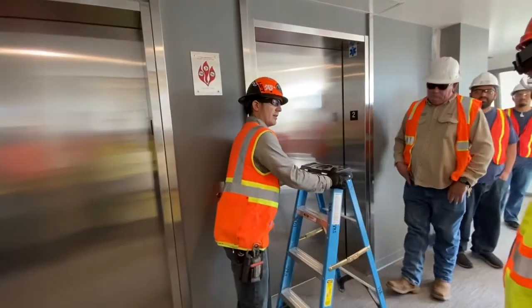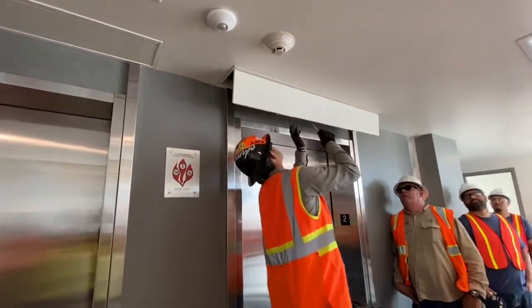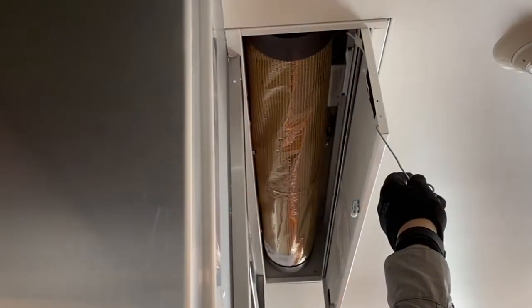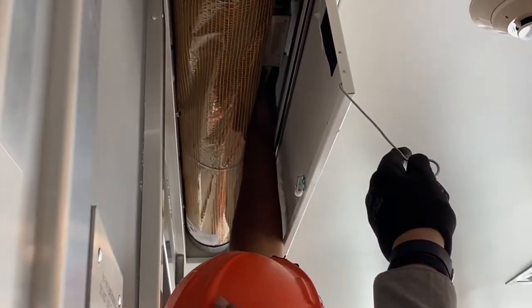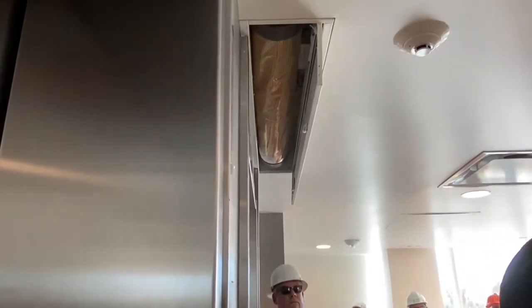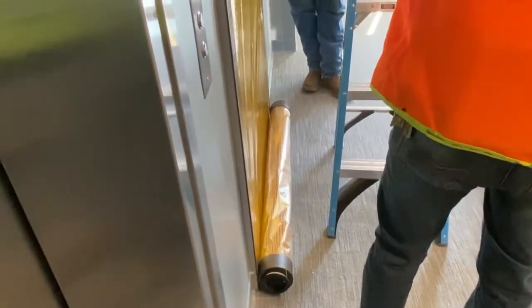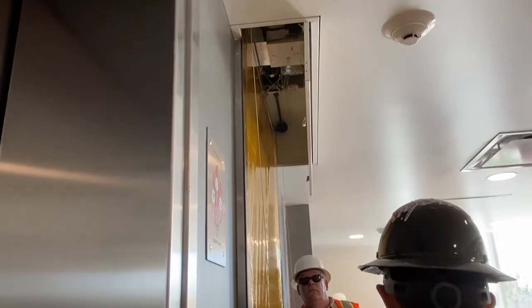Anybody want to try it — just so you can see where we're looking and feel it. You're basically looking for the white box, and then you're looking for the switch. Is there a delay when I hit the switch? Yeah, it'll delay — gives you enough time to get out of the way. You can retract it yourself, make sure that it's tested. You can feel it — it's like a quarter of an inch over, just in case there's any play to it. Then go ahead and turn it back on.